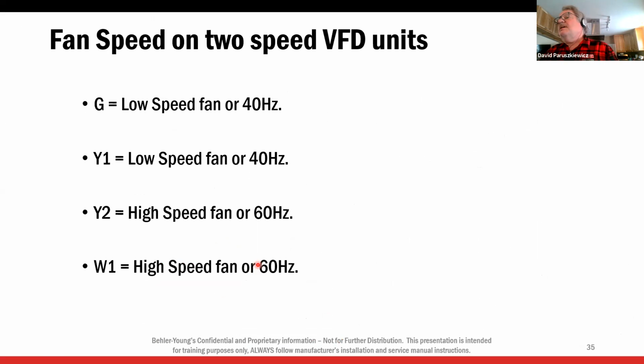problem. All right, so what a VFD does is it takes our AC voltage, turns it to DC voltage, we turn it back to AC, but we control the hertz, right, the speed. Because coming out of Edison, everything's 60 hertz. And that dictates fan speed. So what we're going to do is VFD allows us to change the hertz. All right, we can raise and lower the hertz, raise or lower the fan speed.